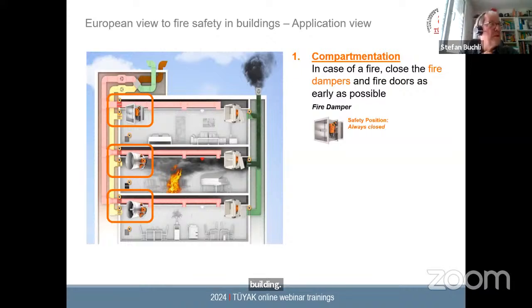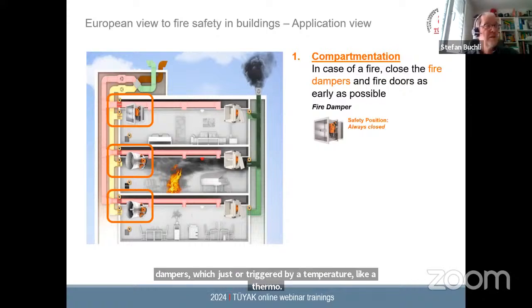As Numan mentioned before, smoke is the killer, so it's really essential at a very early stage in a fire, first to detect the fire and then close the fire dampers so that no smoke can spread throughout the ductwork to other sections, to other zones in the building, but also, for example, to close fire doors, etc. So all openings, and keep the fire in this zone. So this is the first strategy. As you can see here in the duct, in the firewall compartmentation wall, you find the fire dampers. It can be mechanical fire dampers, which are just triggered by temperature, like a thermal fuse, but it can also be motorized fire dampers.